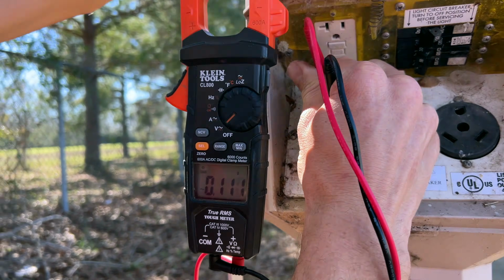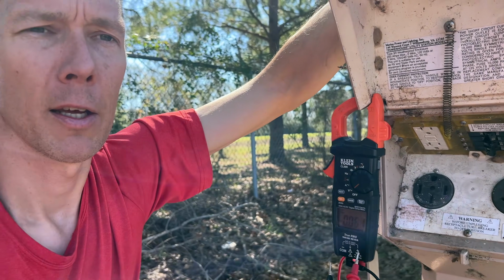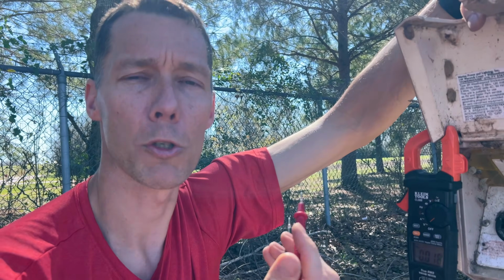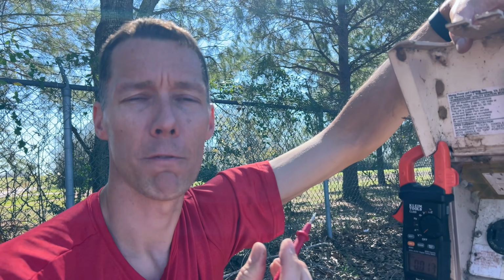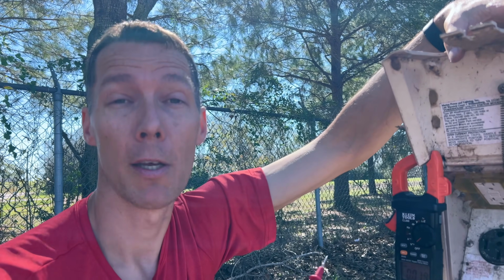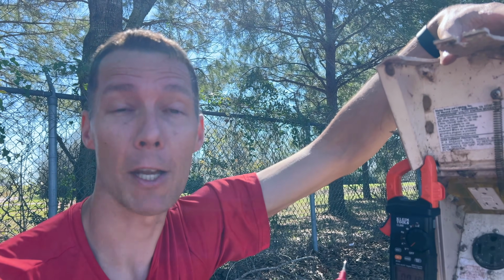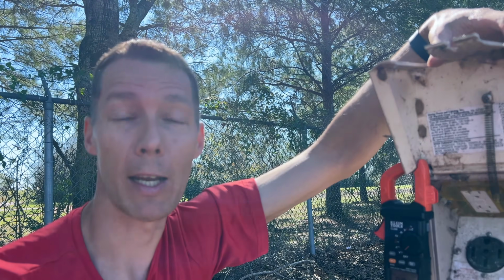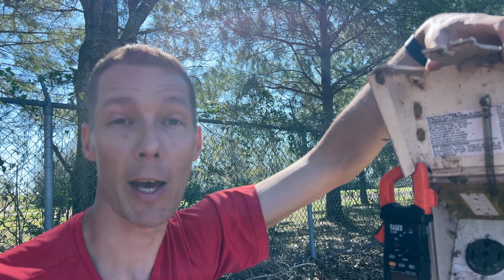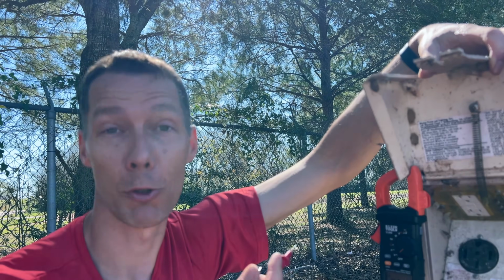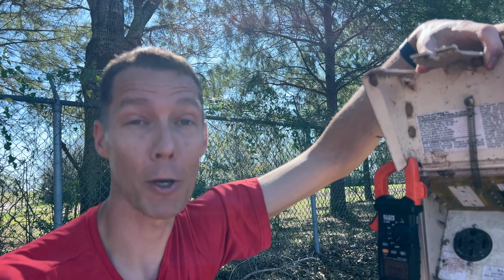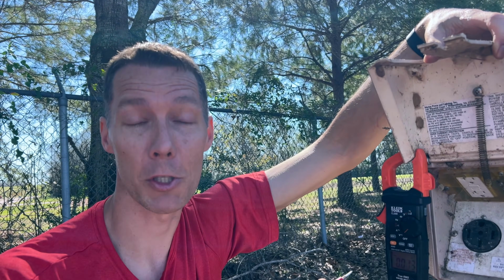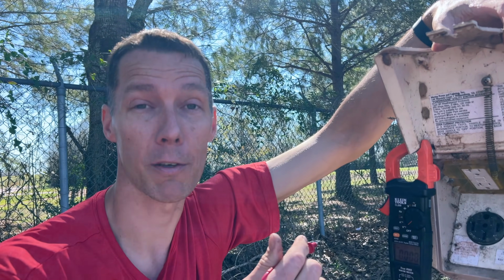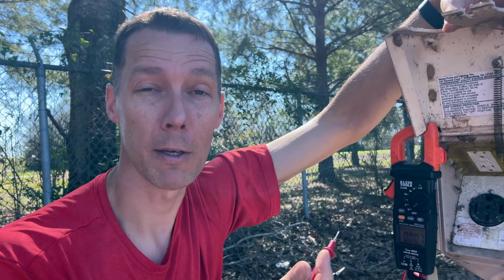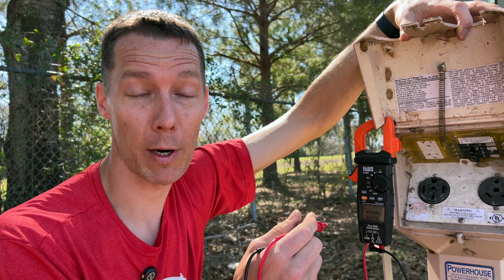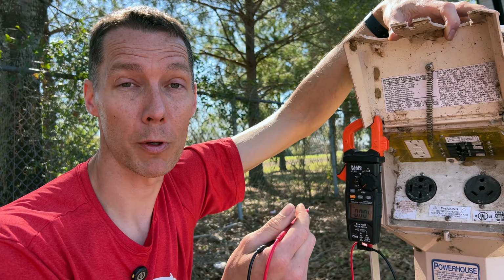Okay, so the voltage is correct. Now if we had improper wiring or loose breakers, we might see voltage that does not read 120. If you're checking between your hots and your neutrals, and you see one side at 280 and the other side at 80, that means there's a loose neutral inside of that plug somewhere. Don't plug into that. You do want to see around 240 between your two hot legs on 50 amp and around 120 on your other readings going around, and 0 between neutral and your ground.